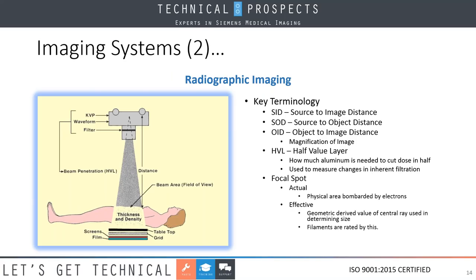So moving on from here, let's take a look at some radiographic imaging. Your picture here shows you typically a radiographic over-table shot going through the patient to expose either the film or our detector. However, there is some key terminology here that we need to be aware of. One is called SID, and this is something that you guys calibrate, and this stands for source to image distance, the source being the X-ray tube, the image being the film or the detector or whatever your system uses. Two other terms that are part of the SID and that are inverse in nature are source to object and object to image. The OID is what controls the magnification of the image. Now, magnification can be both a good thing and a bad thing depending on what the technologist is trying to do.